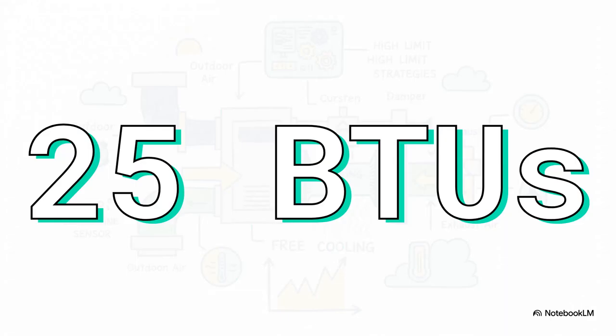And boom, this perfectly illustrates the magic of enthalpy. When we look at the total heat content, that 75-degree indoor air works out to about 28 BTUs per pound. But that warmer 77-degree outdoor air, because it's so much drier, its total heat content is only 25 BTUs per pound. So despite being literally warmer on a standard thermometer, the 77-degree air actually contains less total heat.